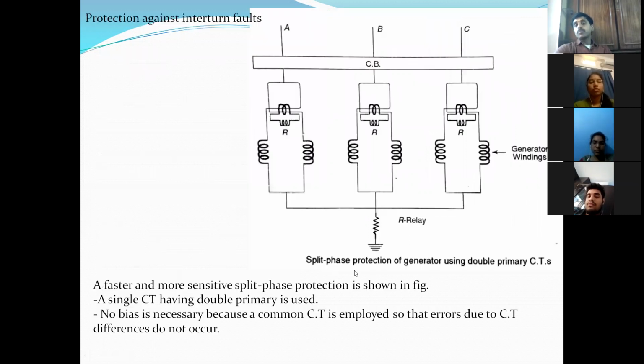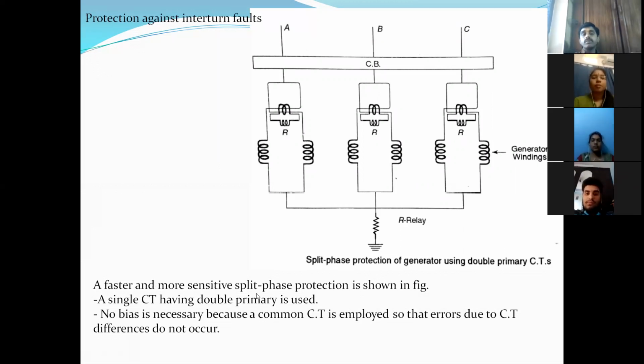So the next scheme is split phase protection. Split phase means here you can see phase A, you can split it into two parts, phase B, phase C. Here you can see the relay coil. There is a CT here, and here the neutral to ground connection through resistance. It is a faster and more sensitive split phase protection, shown in the figure. A single CT having double primary is used. Single CT with double primary. No bias is necessary because a common CT is employed, so errors due to CT difference do not occur. Because normally CT ratio errors will be there, such a problem won't occur. Here, whenever there is a problem between the turns, the relay will operate. The circuit breaker will trip and the generator is protected.